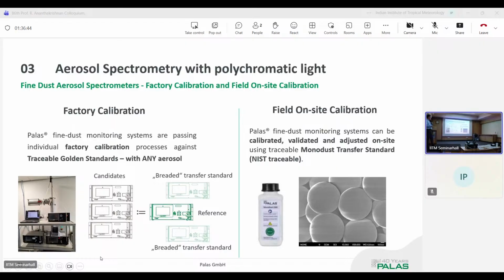Of course, factory calibration. We do monodust calibration in front of factory calibration, and factory calibration is then done against any aerosol, because we are just checking the correctness of the system against the reference system. So we can take any aerosol in this case. We take NaCl as an aerosol, we dispense it, dry it, and then we have a convolution of candidates in a room with additional references, and against those we compare. The PM values and also concentrations should be within plus minus 2% in comparison to the reference instrument. And this is then fixed in the certificate.